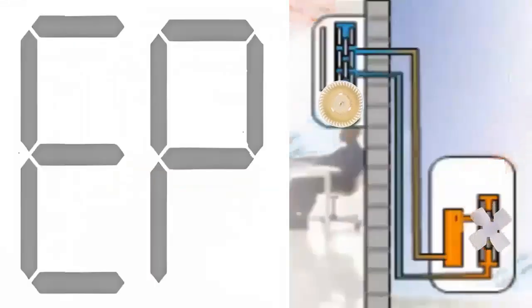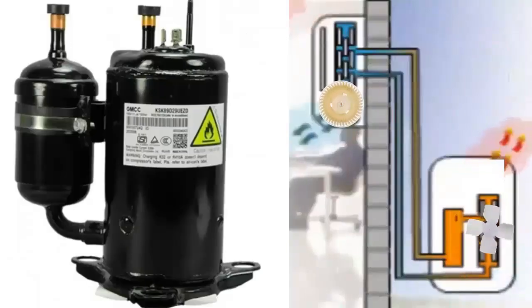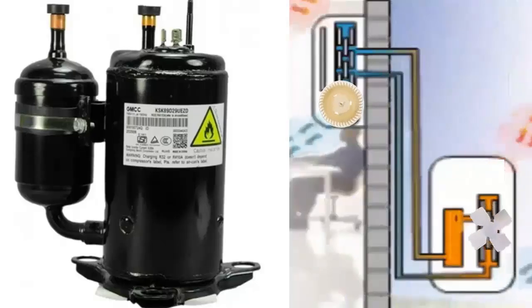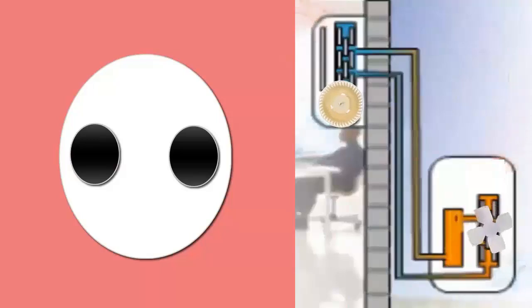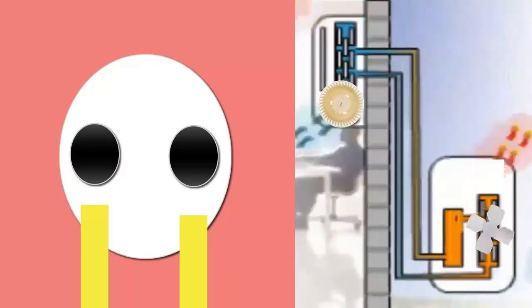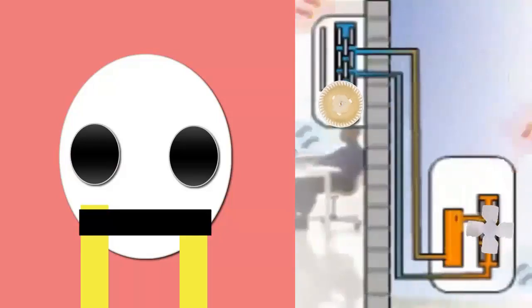2. Missing switch on the compressor. If the EP error appears after a repair, it could be that the switch was not installed. To fix this, create a short circuit bridge, but keep in mind that the unit will be without the high temperature protection system.